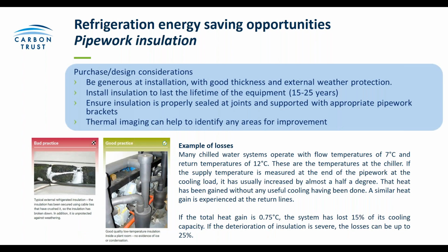Pipework insulation is something that in the short term you might not notice costing you much money, but over the long term it really will add up. Most systems will have this kind of pipework, and if it's not insulated properly, you can see extra heat gains that potentially cost you an extra 15% or even 25% of the capacity of the refrigeration system. So make sure you're generous right at the beginning, with good thickness of insulation delivered across all pipework, built to last for the lifetime of the equipment. If you or your service provider have the ability to use thermal imaging, this can really indicate where you might be having extra heat gains that you don't want in your pipe system.